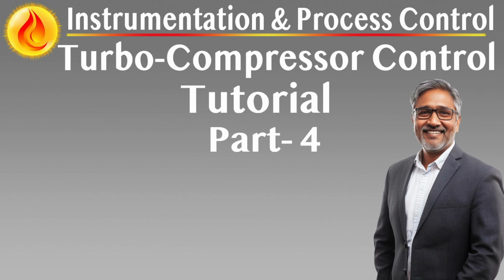Anti-surge controllers. Surge protection loops require total execution time, input to output, of 50 milliseconds or less, high responsiveness to flow disturbances and near surge conditions, and deterministic behavior under multiple active surge loops. Sequence and interlock logic. Safety interlocks, startup, and shutdown sequences must complete total logic scans in less than 100 milliseconds, maintaining full performance even when all auxiliary systems, valve interlocks, and permissives are active simultaneously.